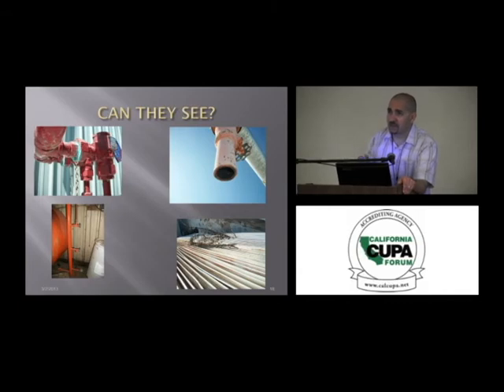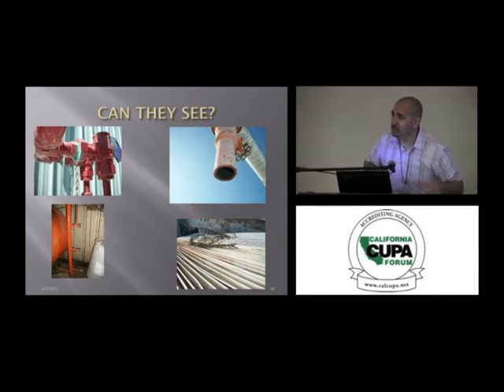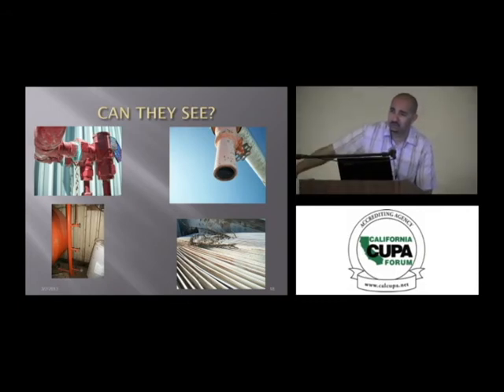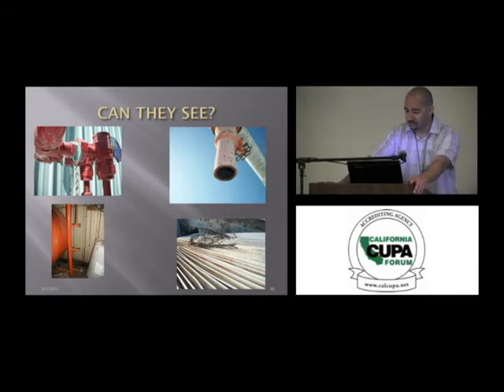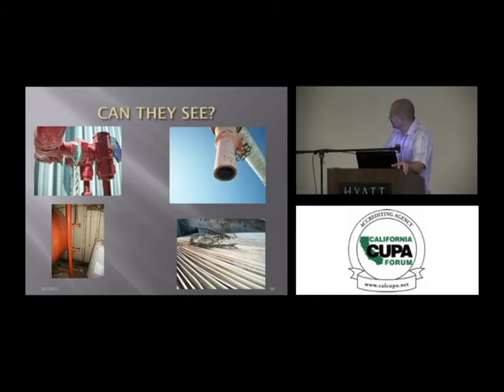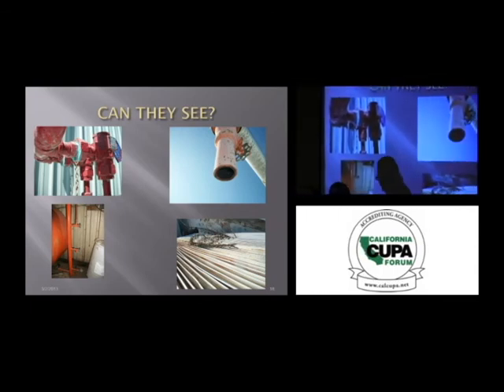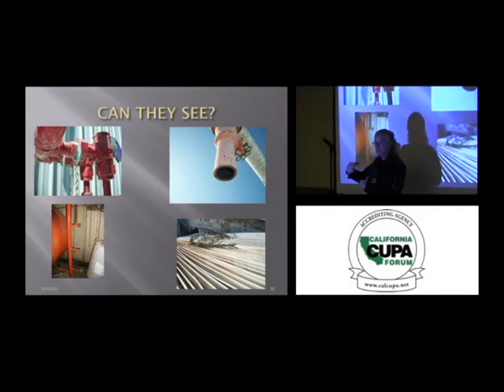That's just thin glass. I knew of a story of a gentleman that was cleaning the engine room. He's sweeping away. When he went back with his broom, boom, he pops it, causing an ammonia release. Yeah, it's real thin. Basically, this is one of those things where if you see this type of sight glass, the top section there, in a facility, recommend that they replace it with armored bullseyes or armored plate glass. There's little grommets here that are used to secure that, seal that to that tube, and when you get small leaks, they'll just tighten those up. Well, they tighten them up too many times, they crack the glass.